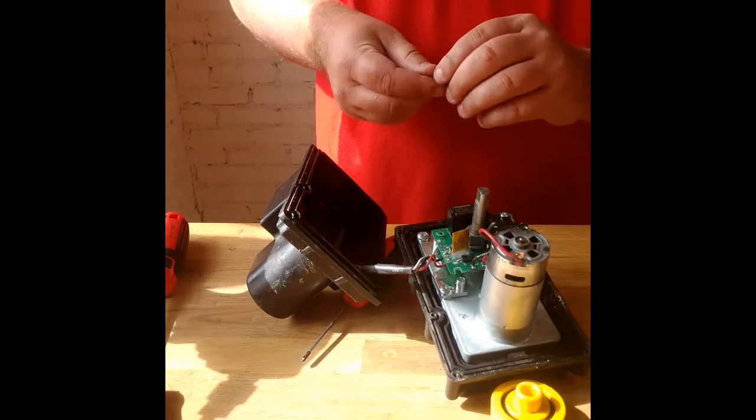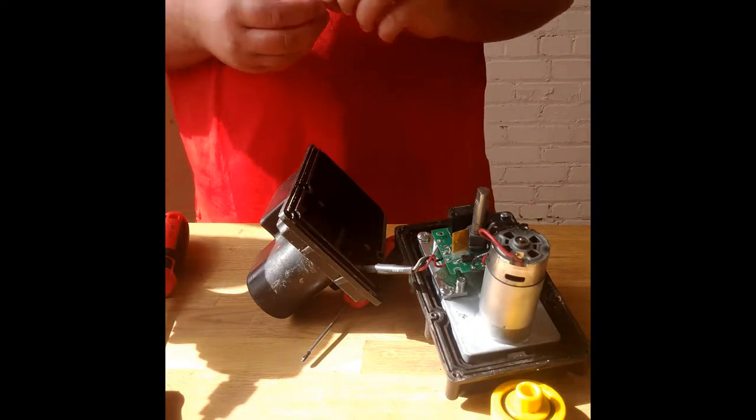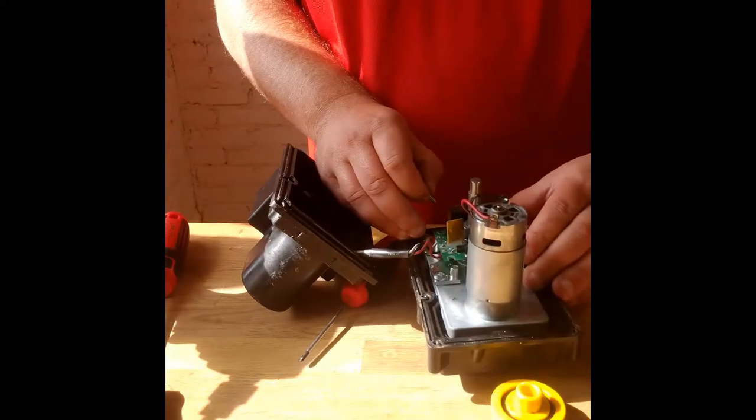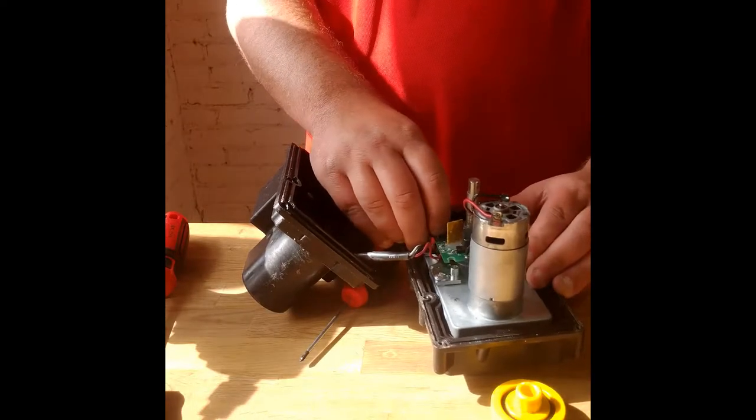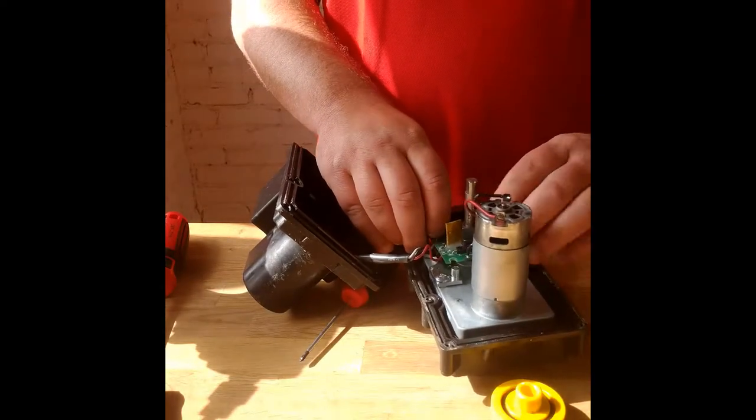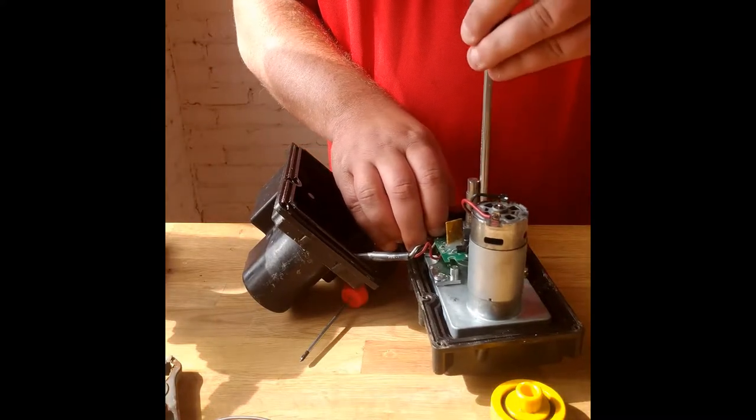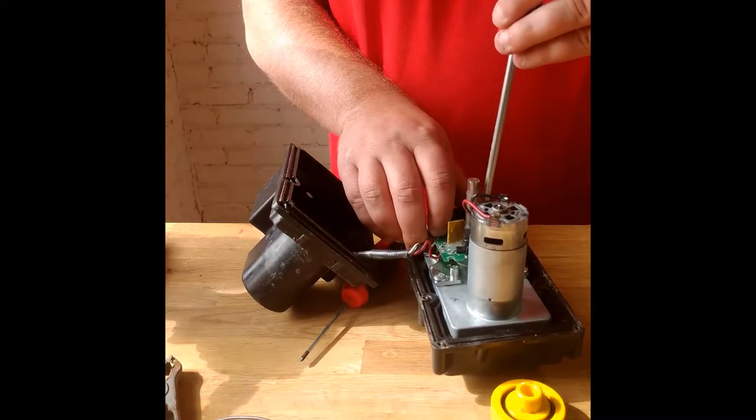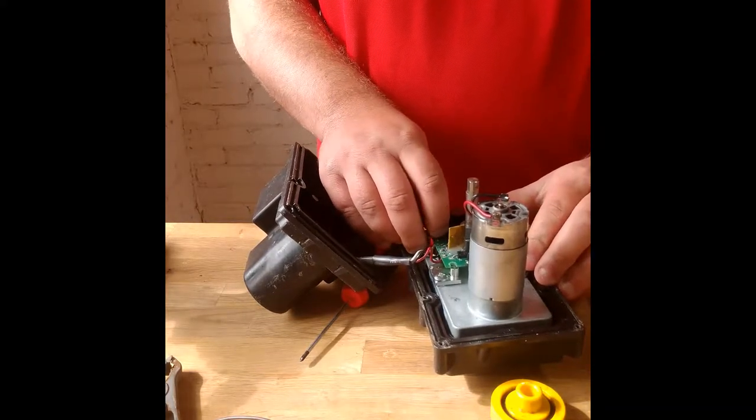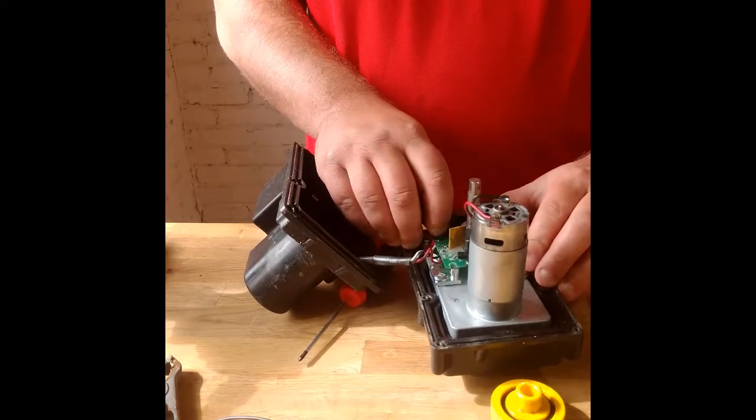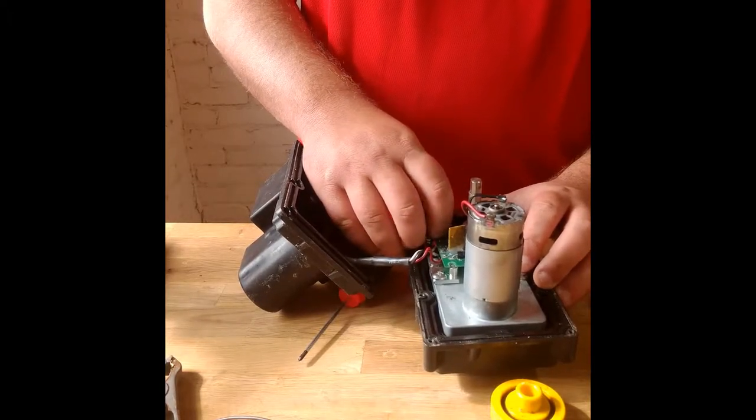And it's really just the same process in reverse, put your four screws in. The one thing I will note, if you want your valve to open a little differently, you can change those half moon shims on that output shaft where those position switch sensors are. So if you have another use for this top you can get it to do basically anything you want in terms of on and off positions by moving those shims around.